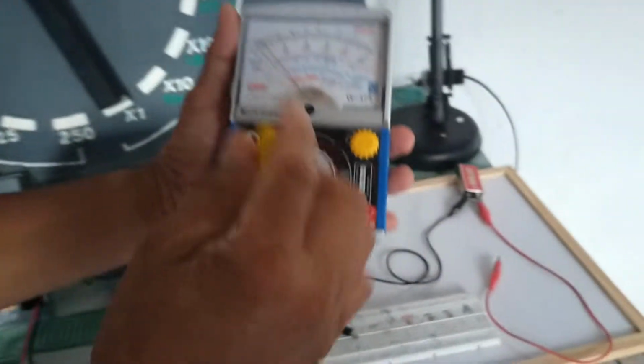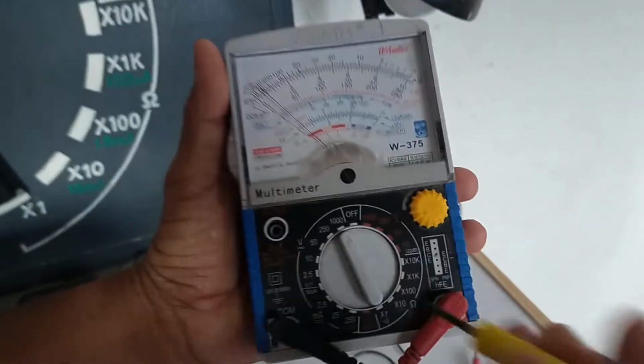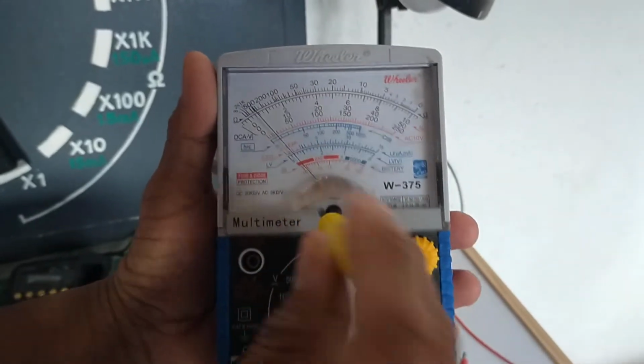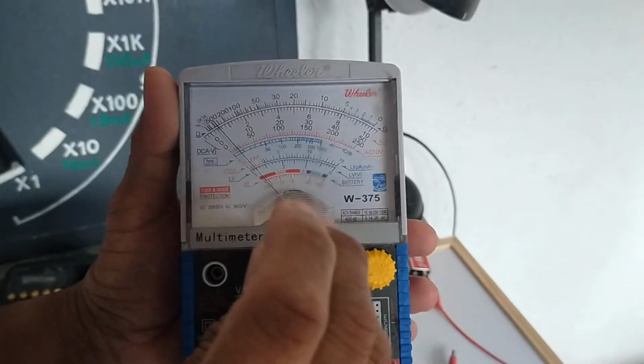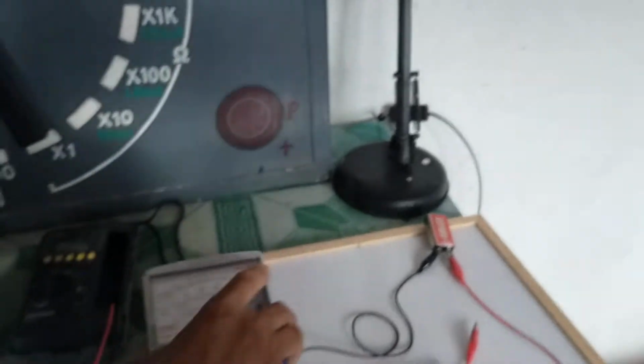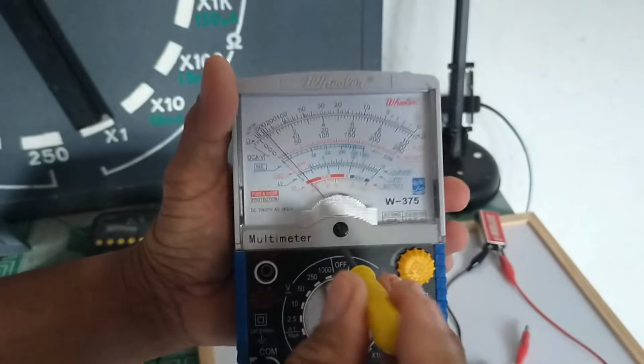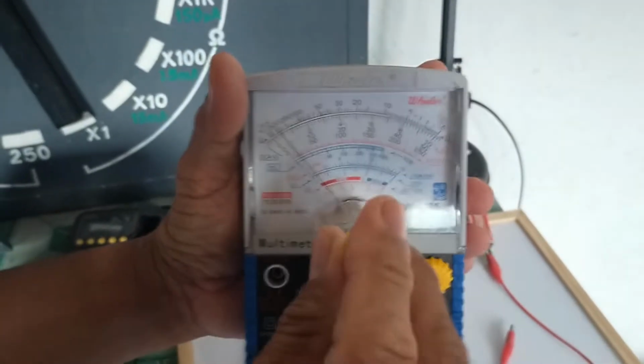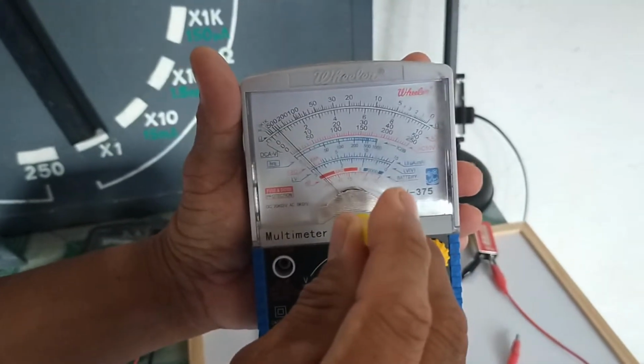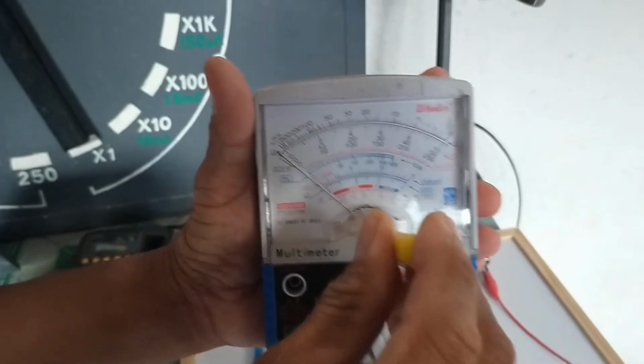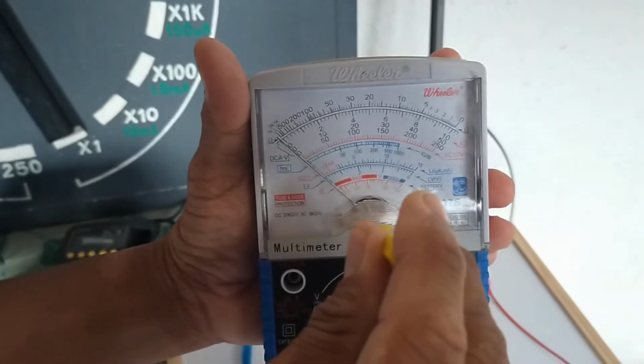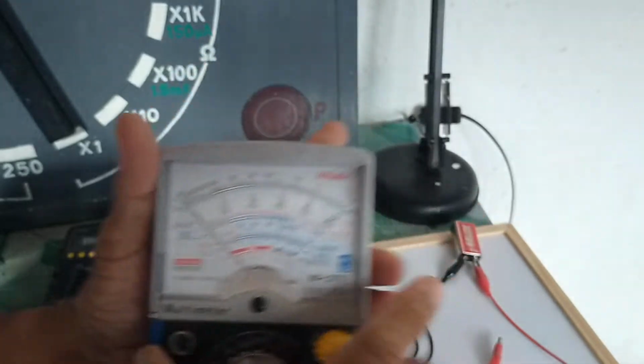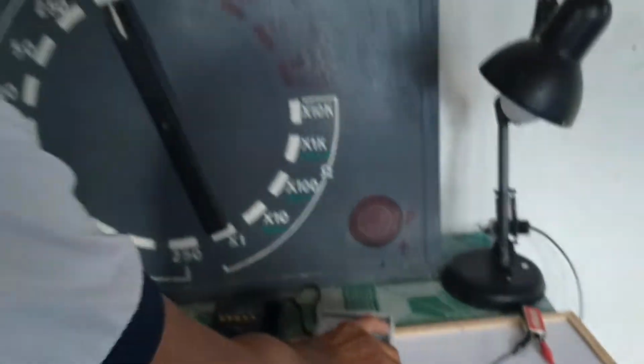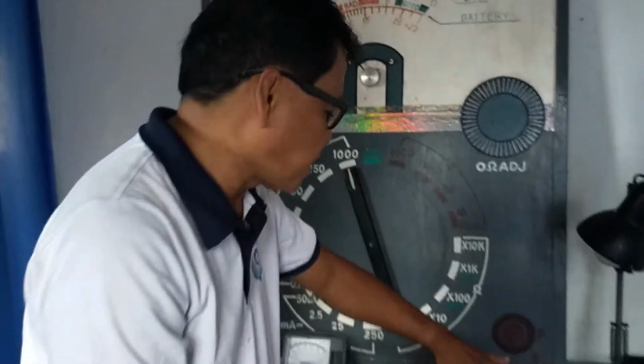First is to set the 0 set screw with the aid of this minus screwdriver. Just insert this minus screwdriver to the slotted head of the screw set, just like this. Rotate this one clockwise or counterclockwise to set the deflection pointer at 0 scale, just like that, to obtain accurate reading of voltages and currents.